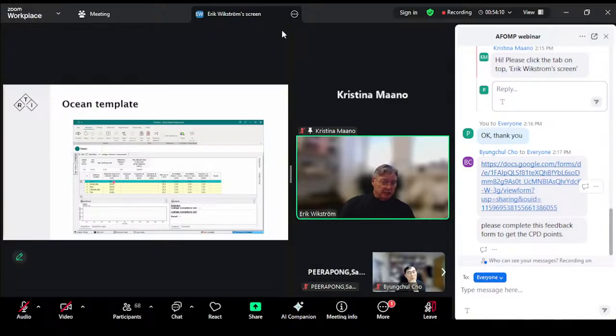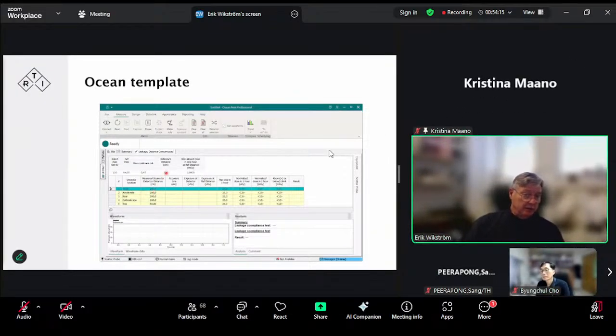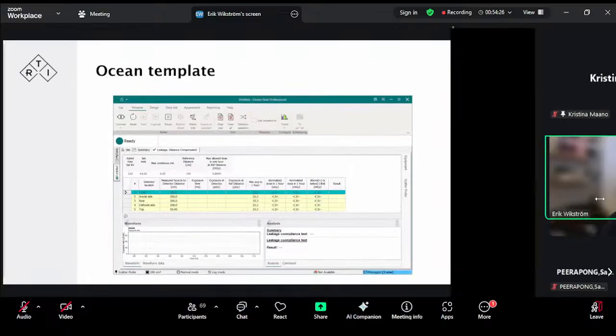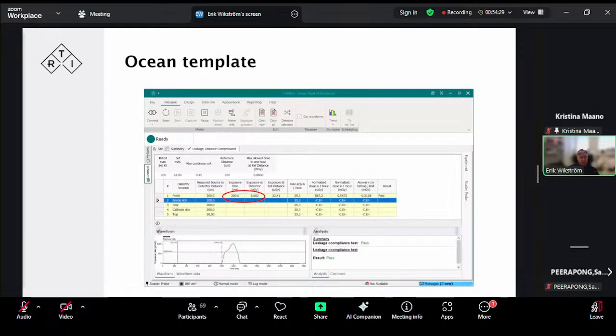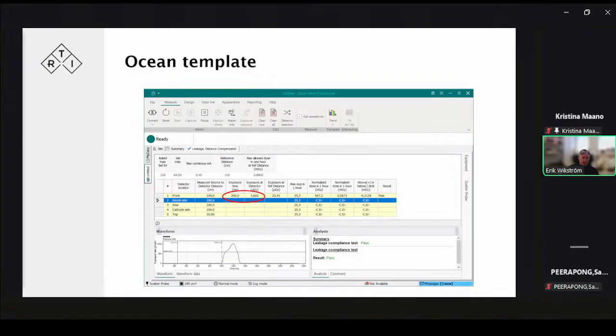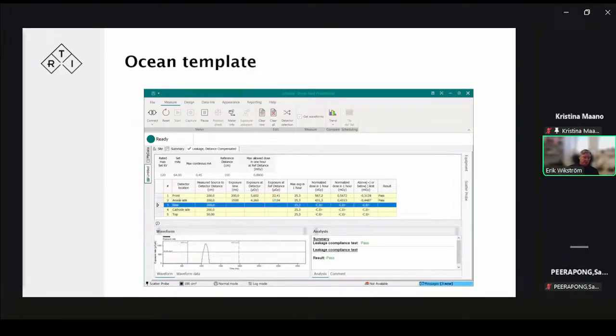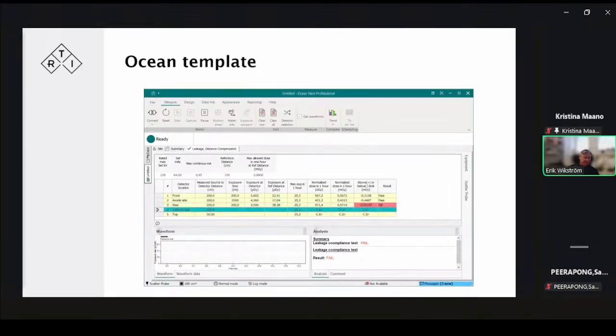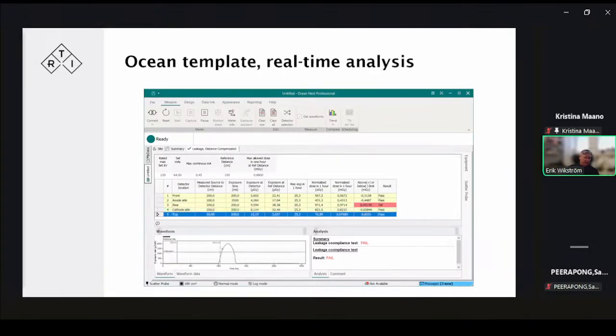We position it here, and wherever we can, we let it know that the reference distance is 100 centimeters, that's 1 meter. So if we can place it at 1 meter, that will be fine. Then we'll be positioning it here, and then we just make exposures. The data is collected and populated directly from the scatter probe into the template. The readings are made, and recalculations are made in here automatically based on the inverse square law.